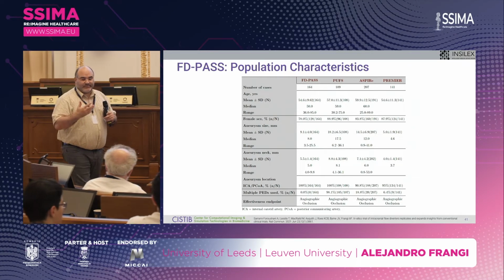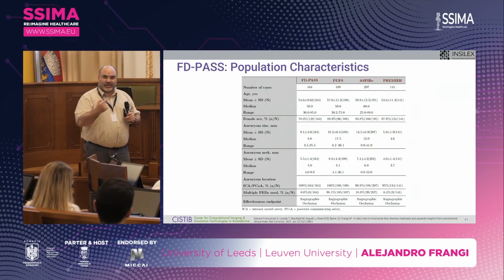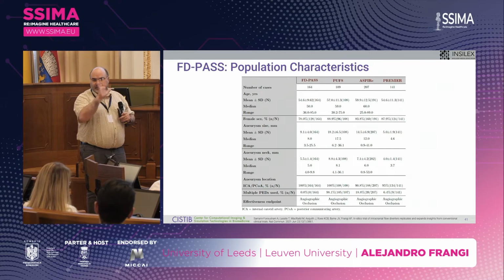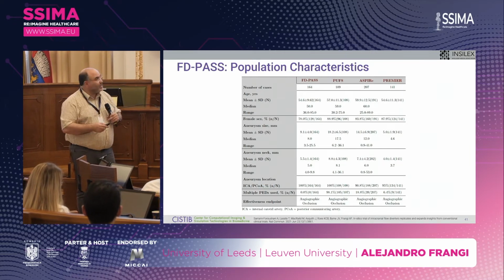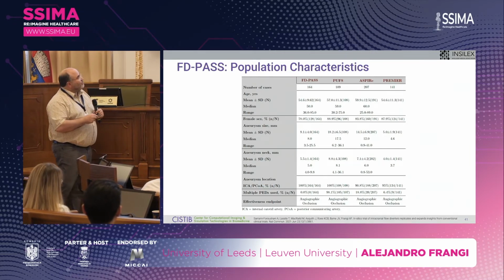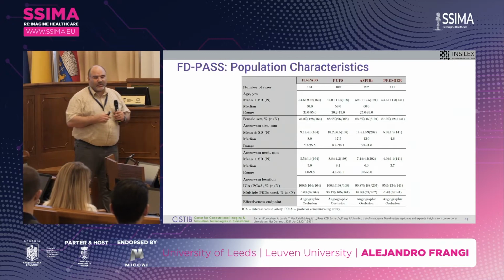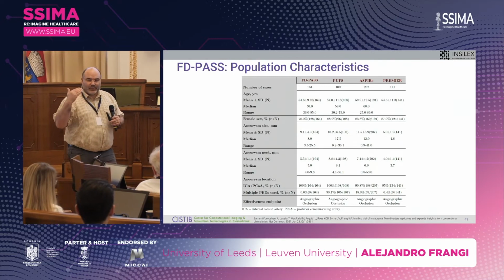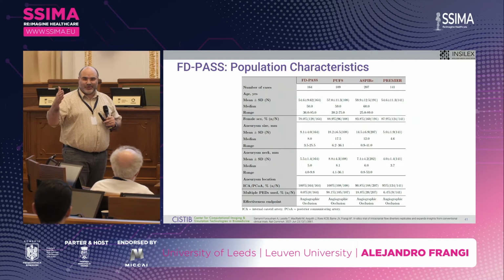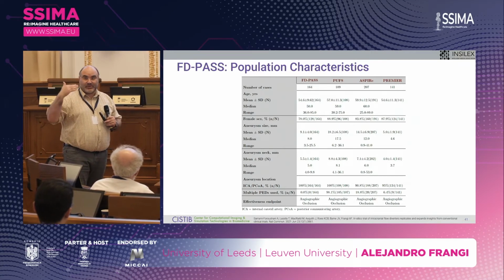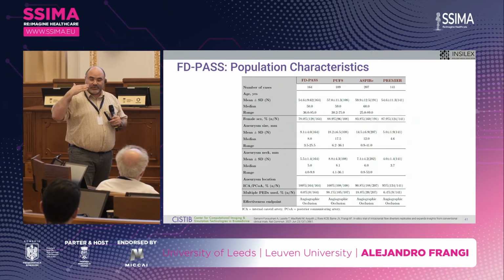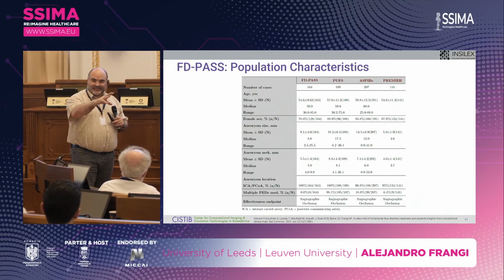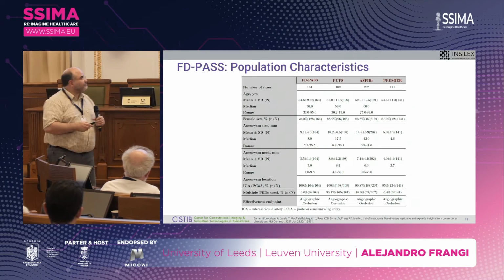If the device hasn't done a good job, then contrast gets into the aneurysm and you will see the aneurysm lighting up, okay? So we did the same, but in this in silico way. We have to solve the transport equations for the contrast bolus into the aneurysm, and do essentially a ray casting that gives you an idea of what the X-ray signal would be.